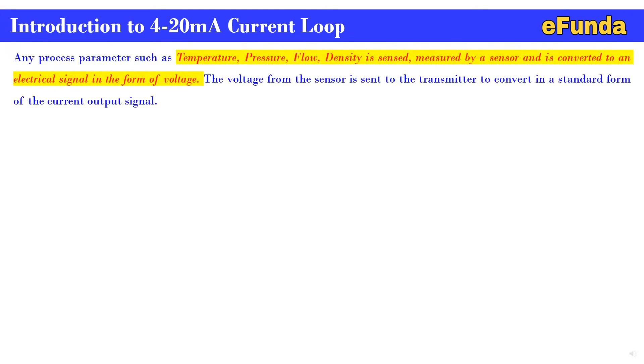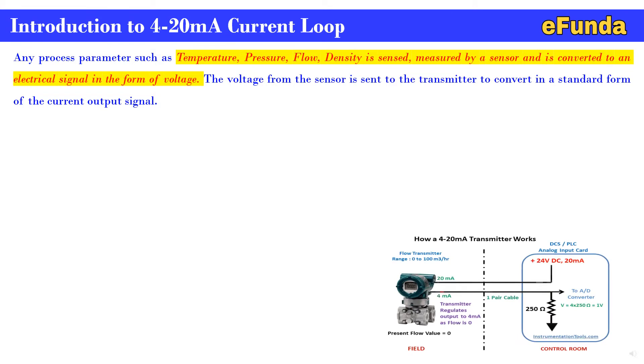Introduction to 4 to 20 milliamp current loop: any process parameter such as temperature, pressure, flow, or density is sensed and measured by a sensor and converted to an electrical signal in the form of voltage. The voltage from the sensor is sent to a transmitter to convert it into a standard current output signal. One can refer to the animation where the transfer of current from the field sensor is sent to the control room.